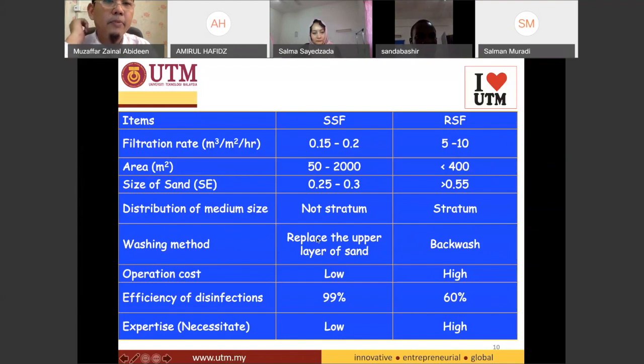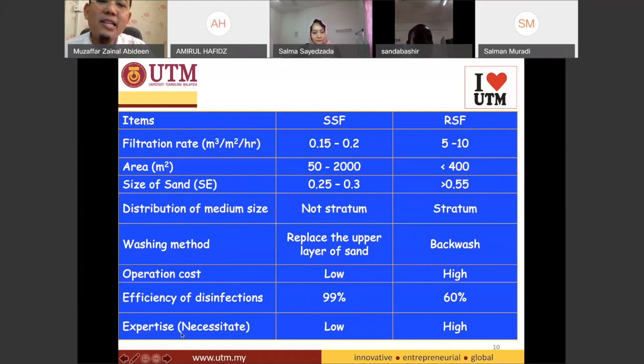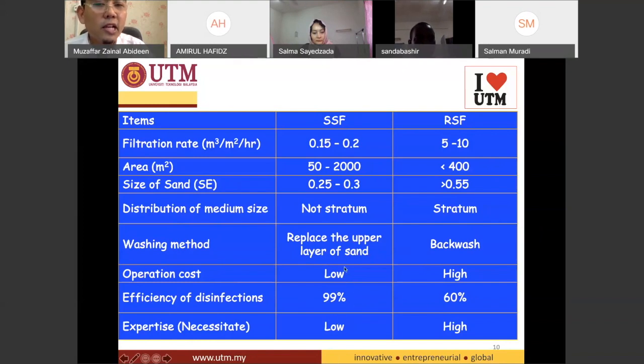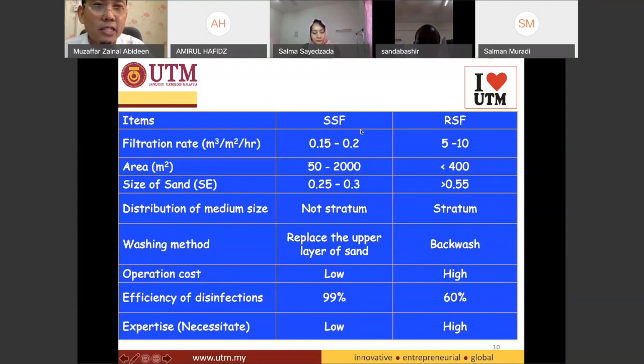The operational cost of the SSF is low, and its disinfection efficiency is a lot higher than the rapid sand filter. The expertise required is also low. So the slow sand filter seems very good — it disinfects well and has low operational cost. However, because it requires a greater area and the filtration rate is very slow, it is not as popular as the rapid sand filter.